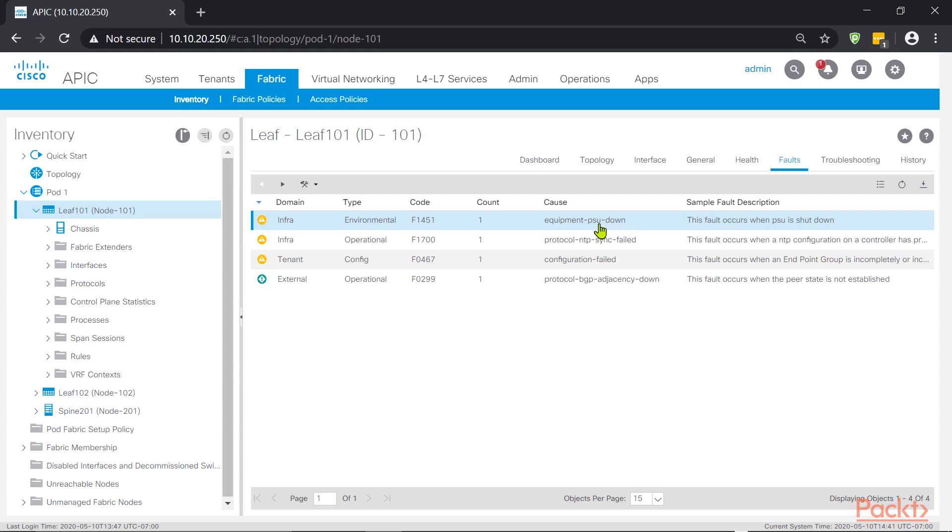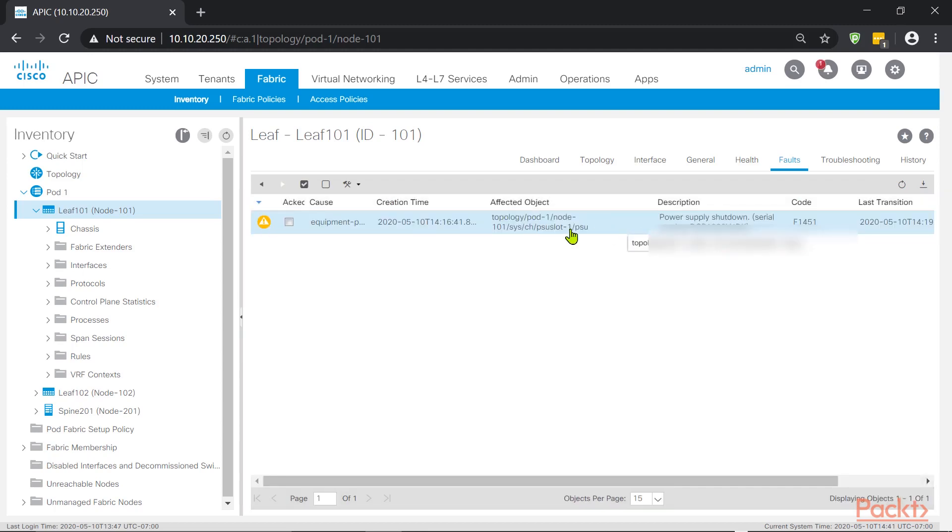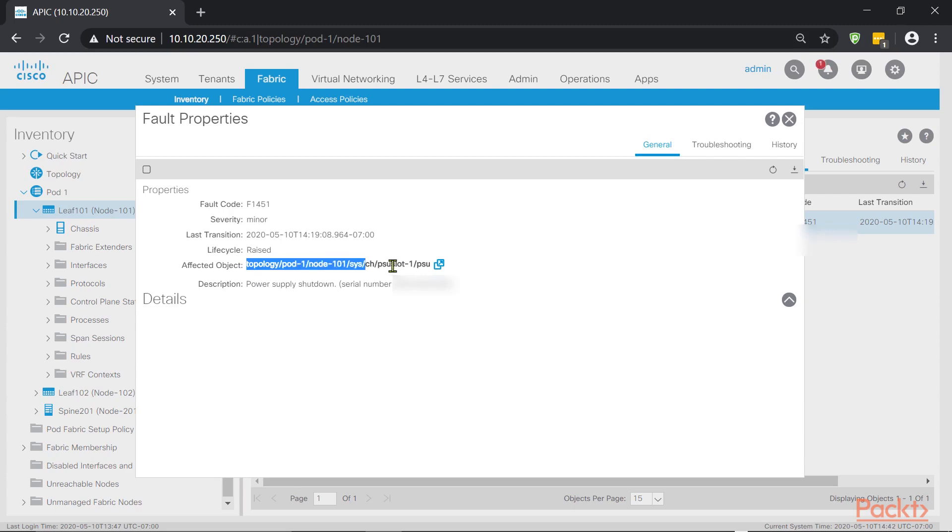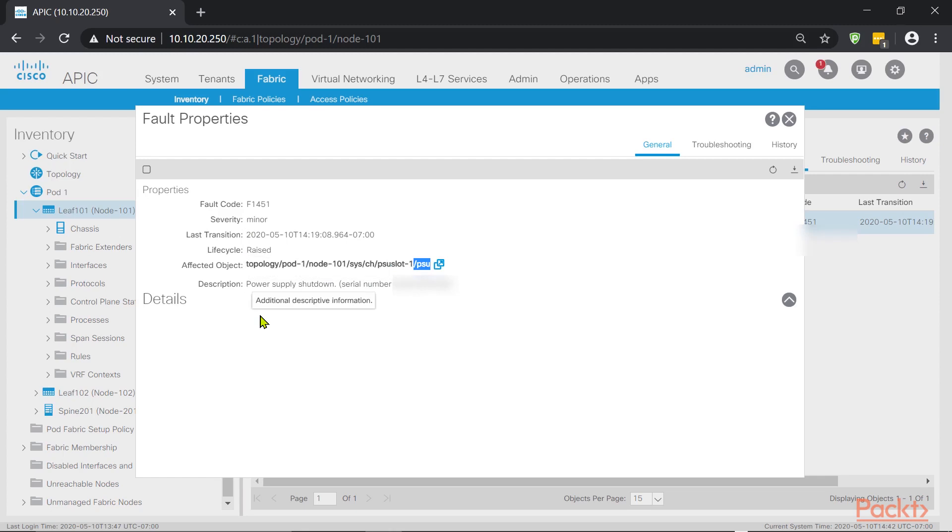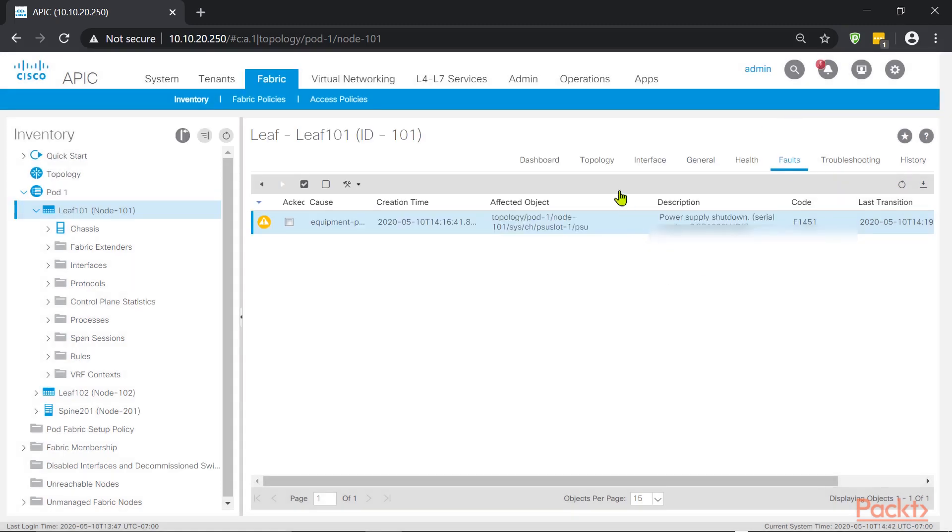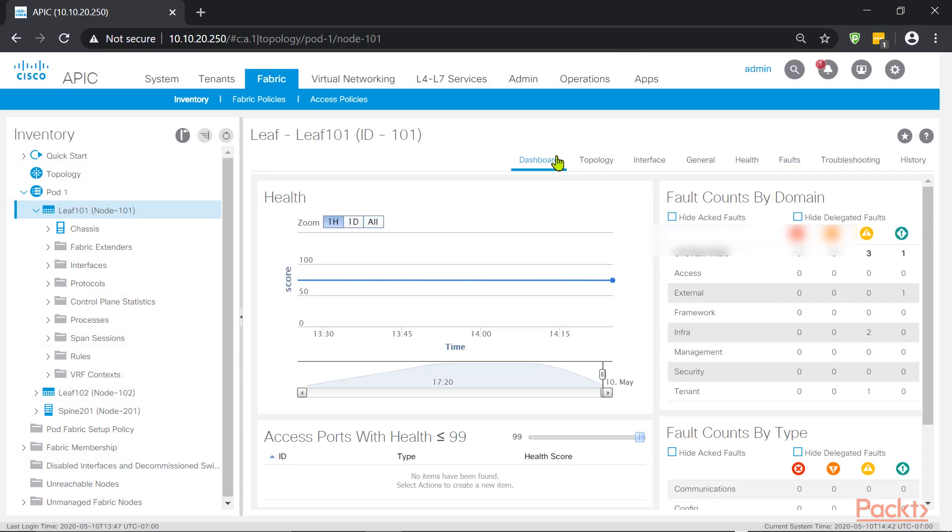So it's telling me, hey, you're not redundant when it comes to power supply. If we want to see more information, we can just double click the actual fault. And it actually tells us exactly what it is. It goes all the way into the path of that particular object, in this case the power supply, and tells us what's going on. Power supply is shut down. And if there is resolution, which in this case we know what we need to do, it also tells you what you can do about it. This is one way of seeing the health score.